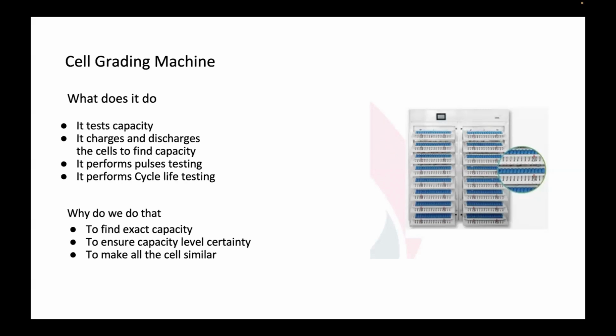This comes in different capacities. For 18650, normally 3 ampere machines are used. For 21700, normally 6 ampere machines are used. Now we also have machines for 10 amperes, 15 amperes, 20 amperes, and 30 amperes, because 30 to 140 cells come in the 15 ampere capacity, and many people who want to do grading, charging and discharging at 1C rating buy the 15 ampere machine. This goes up to the 1000 ampere category, so you can have different configurations of machines for cylindrical, pouch, or prismatic cells.